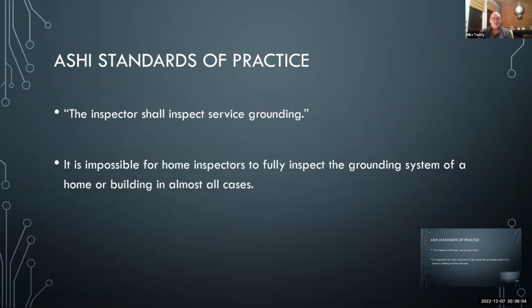It's impossible for a home inspector to fully inspect the grounding system of a home or a building in almost all cases. The reason for that, most of it is below ground. And I say that in that ground rods are supposed to be driven to a certain depth. Unless you've got a shovel or a backhoe, you're not going to confirm that it's proper.